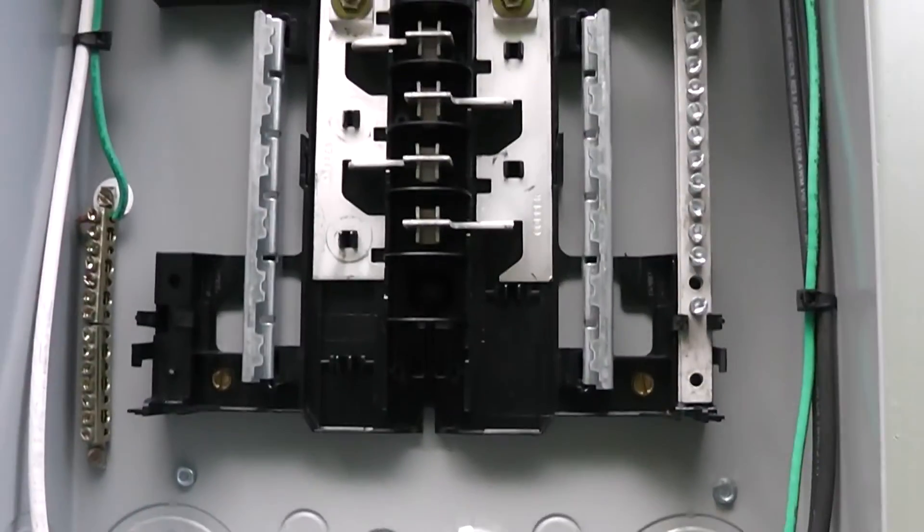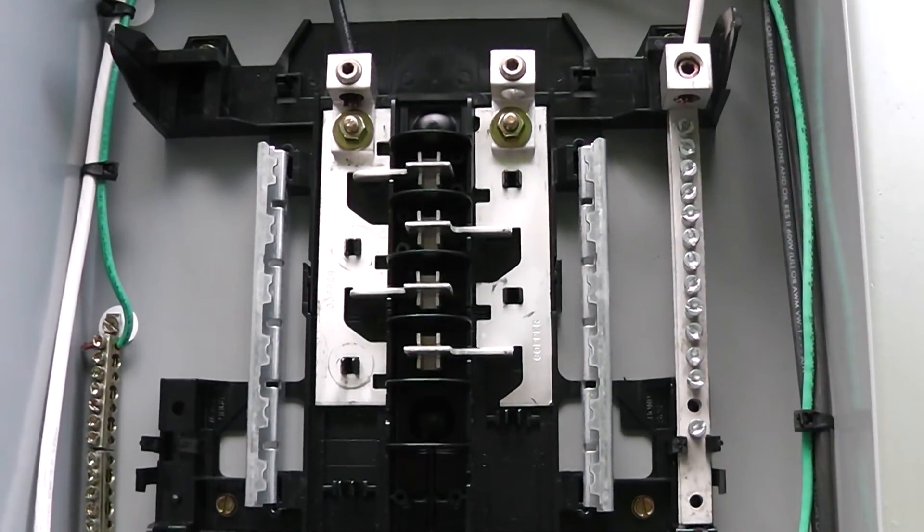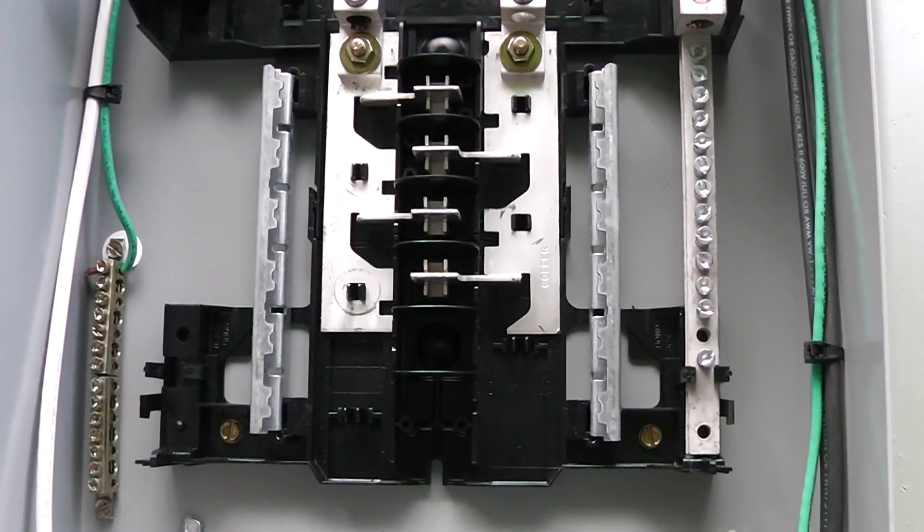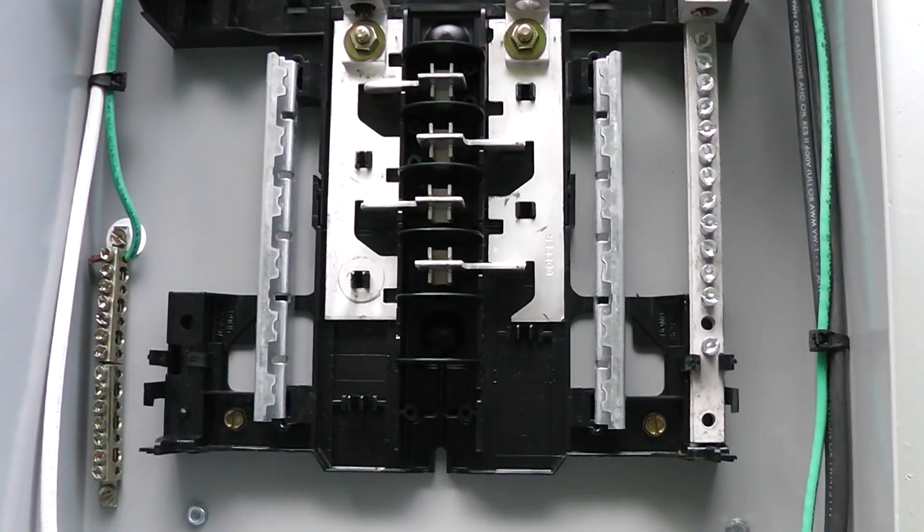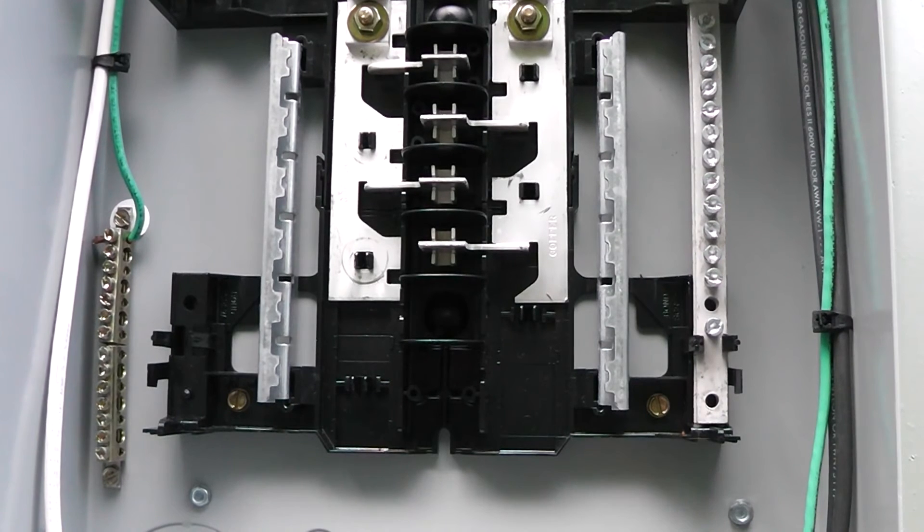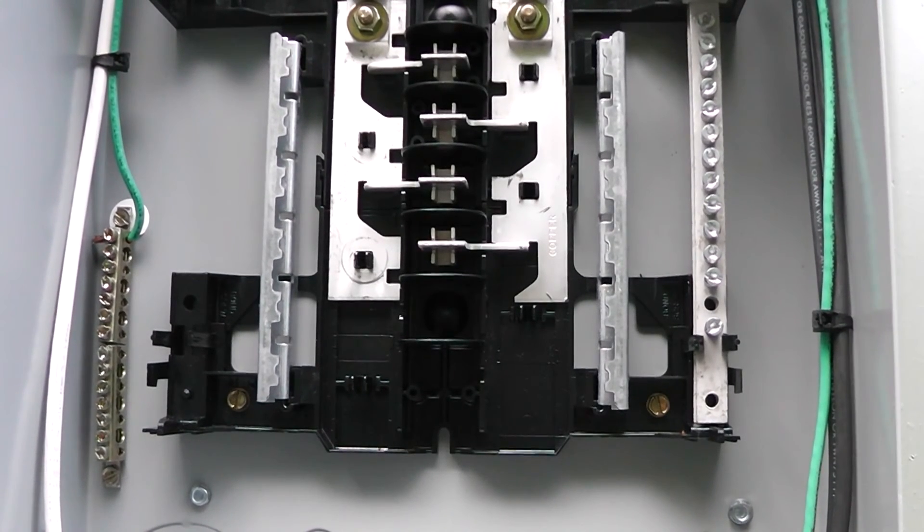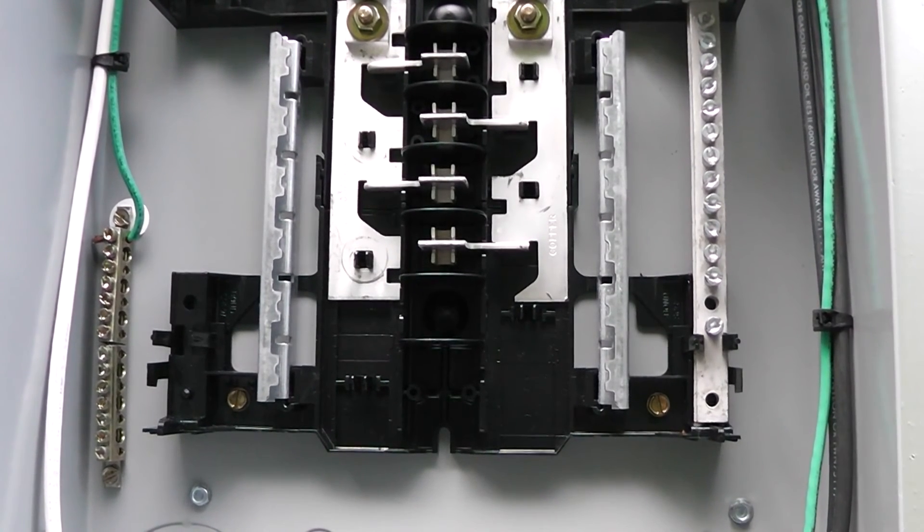So I think if you address those problems in your sub-panel and do what we did here in the beginning of the video, separate the grounds, the neutrals, and put in a grounding electrode conductor, I think you'll be good to go. If you have any more questions, send me an email.